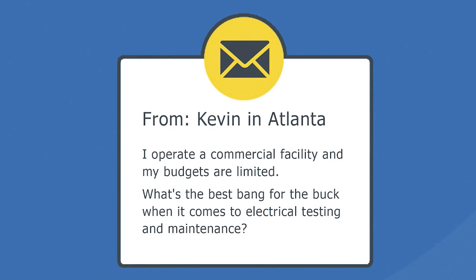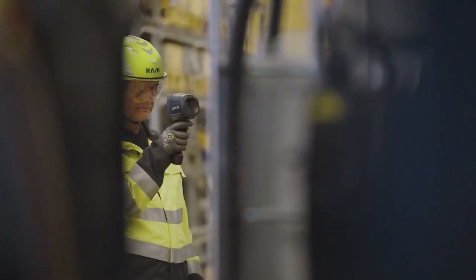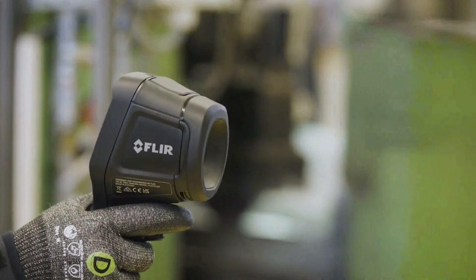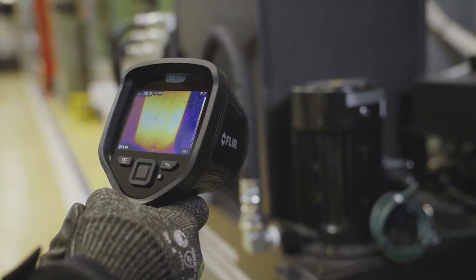This time we got a question from Kevin, and Kevin asked, hey, I operate a commercial facility and my budgets are limited, so what's the best bang for the buck when it comes to electrical testing and maintenance? The first thing you want to do as the maintenance professional at a facility is do infrared or thermographic surveys. And I'll tell you, it's the best bang for the buck because the system's online, it's energized, and you're going to find a ton of problems while doing the infrared surveys, guarantee you.